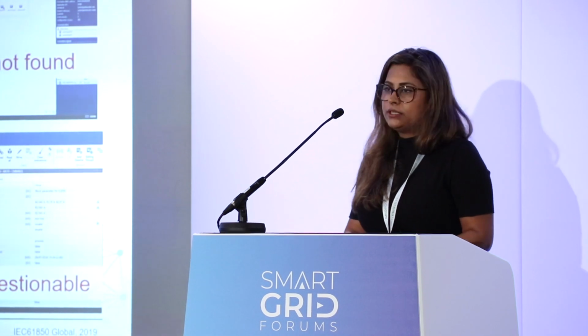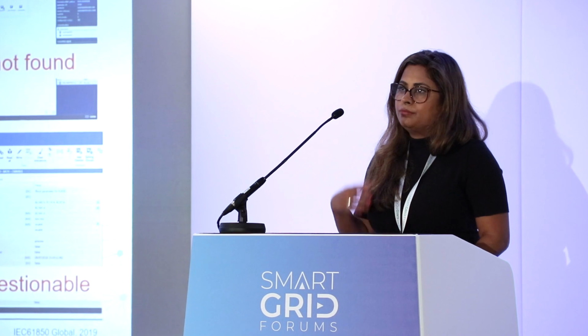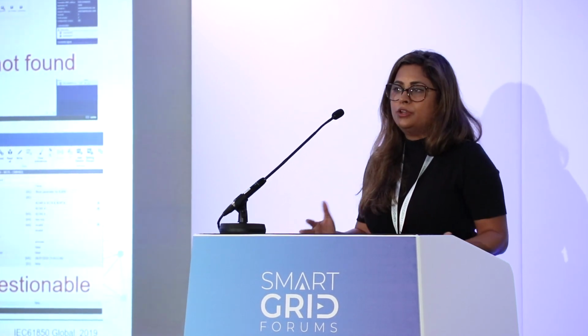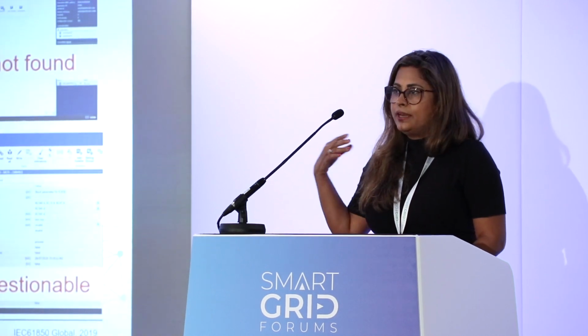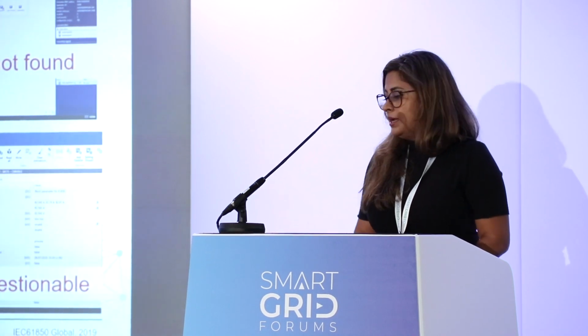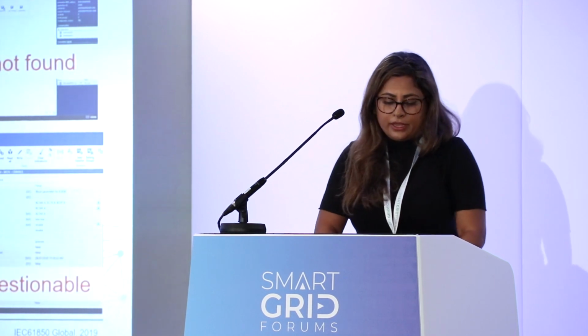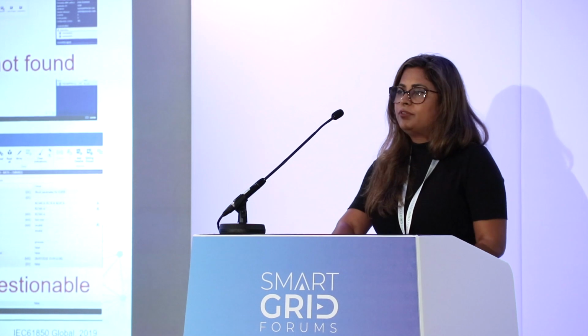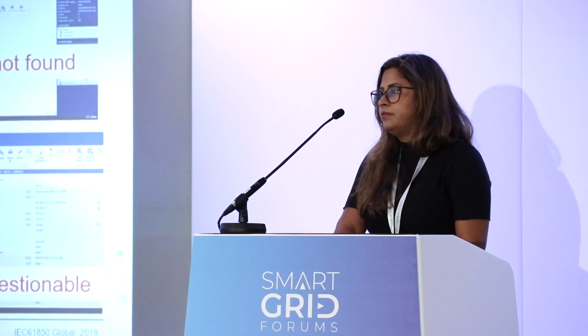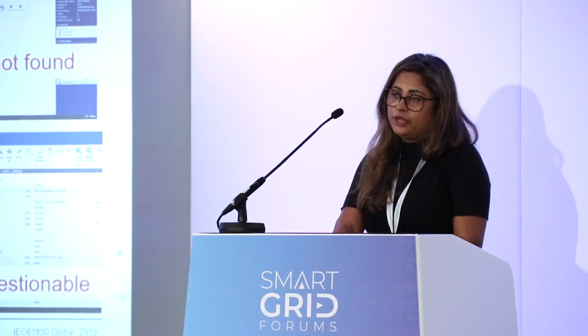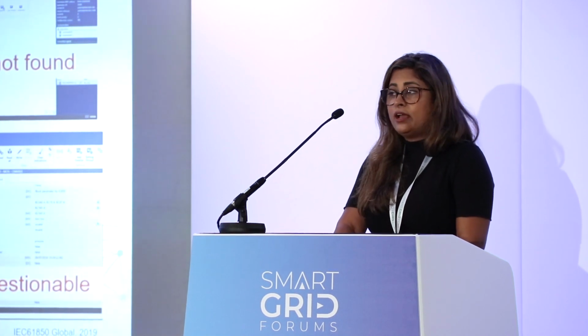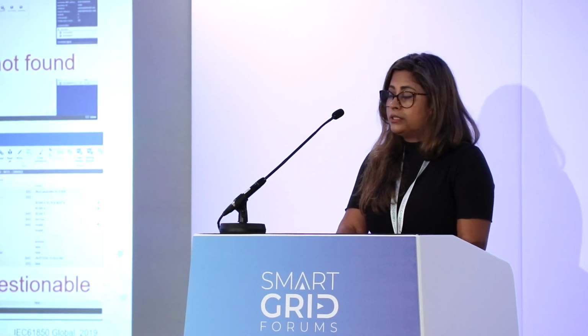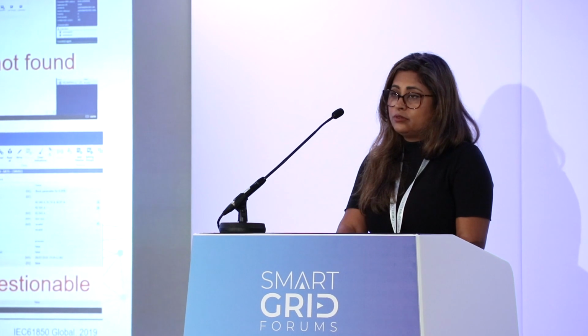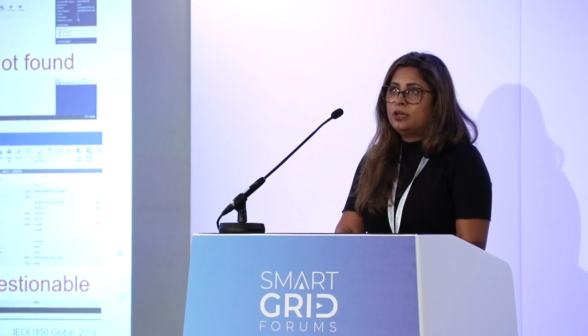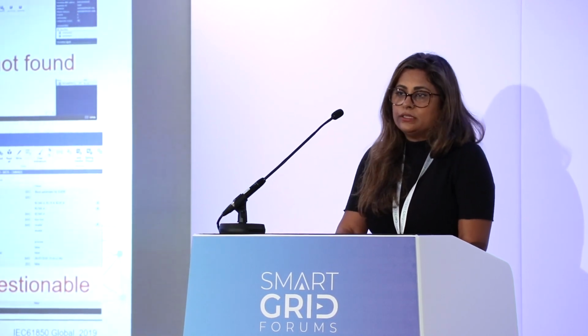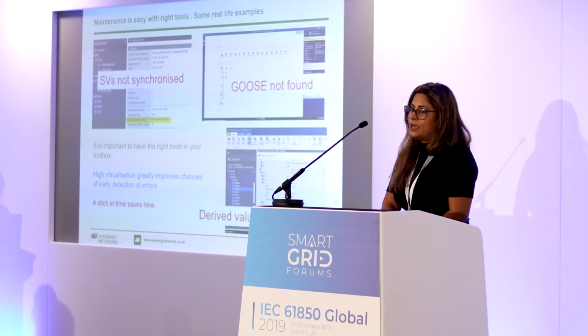Sometimes these issues don't cause problems because they don't come into play until there's a fault on the network, and they can go unnoticed if you're not regularly checking. So tools enable you to identify issues before they become failures - as I said, a stitch in time saves nine. With digitalization, communication networks, and better visualization, you now have the power to really see what's going on - something that wasn't possible with hardwired IEDs. With a hardwired IED, unless it specifically monitors and reports an issue, you'd never know about a failure until there's a fault. But with digital substations, you can drill down and see what's happening, enabling predictive or condition-based maintenance - seeing issues well ahead of time and doing something about it.